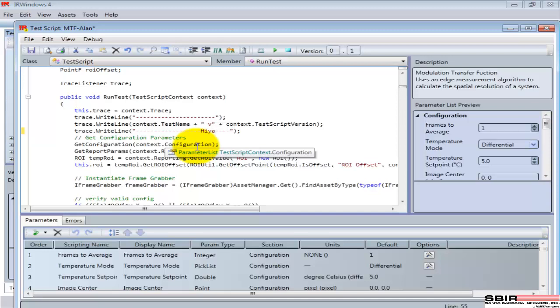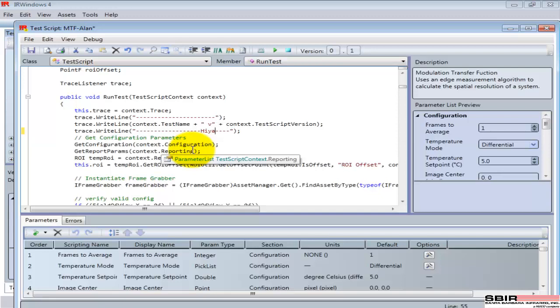So if you need to make spot changes, like for instance, the data's been collected and I want to run a special filter because I know a second-order filter needs to be run before my MTF, I can make that alteration. If I need to send a command to my unit under test, the device that I'm running, because I want to change, for instance, the field of view, I can do that. I can add whatever I need to to this code and configure it for my specifications.